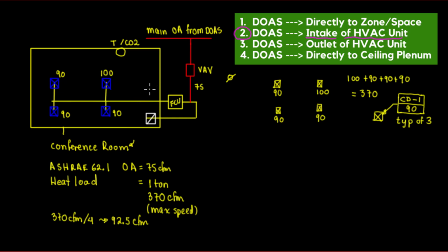Okay, so the main issue in here, and the reason I'm making this video, is that I've seen in a lot of projects, in videos also, that they don't pay so much attention to this. I'm going to put this in pink because this is very important. They don't pay attention to putting the CFM on the return. I've seen projects where they just put return grill 1 and then a dash. The dash is very interesting because they leave it to the contractor. The contractor is going to size it and just put a grill, but as designers, I think it's a good idea to put on the CFM sometimes, right? So let's put on the CFM of the return grill, and that's the part that is sometimes confusing. What's the CFM on the return grill?